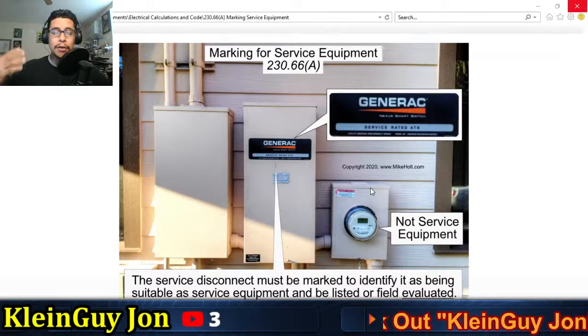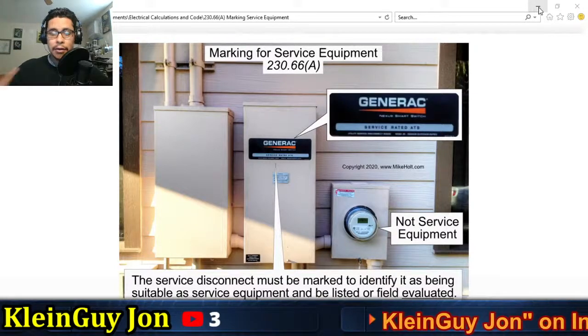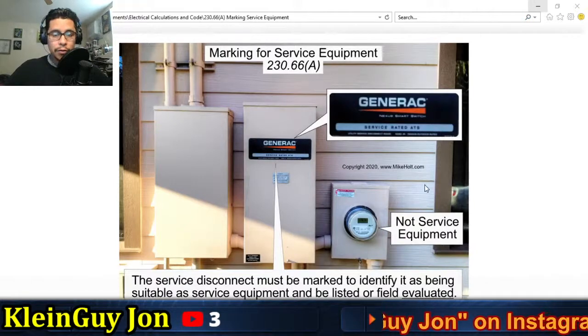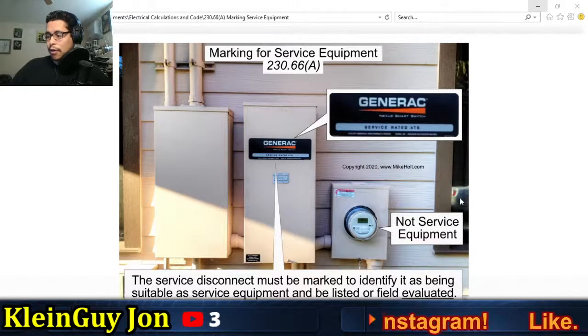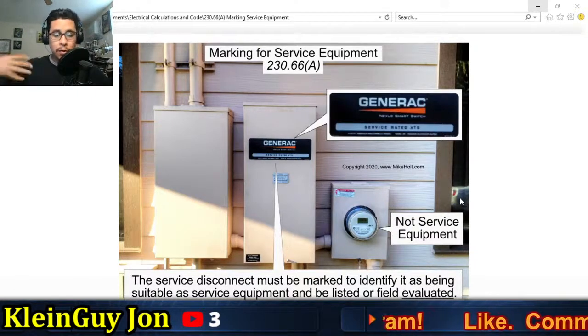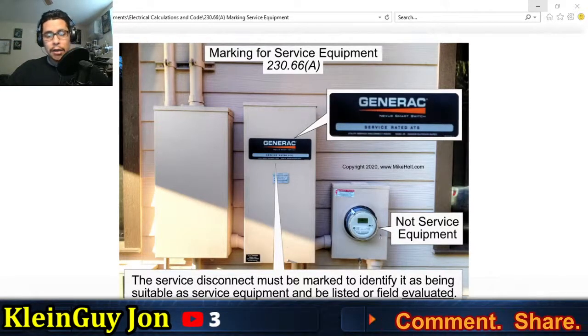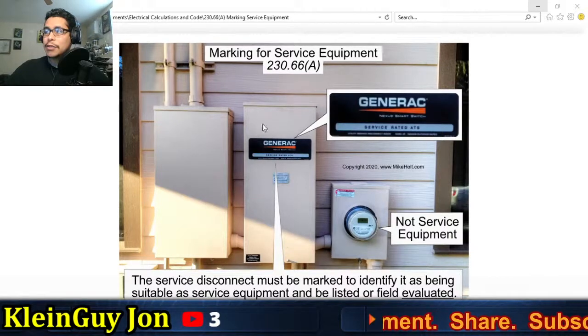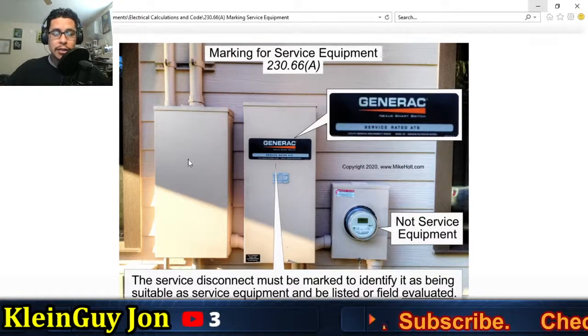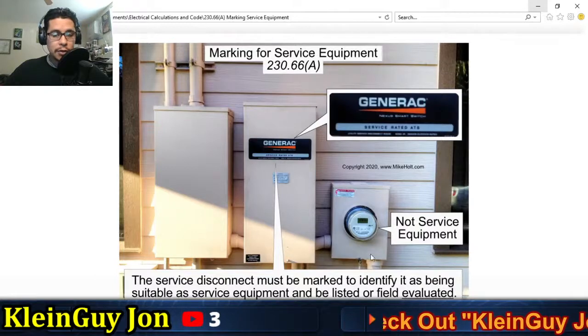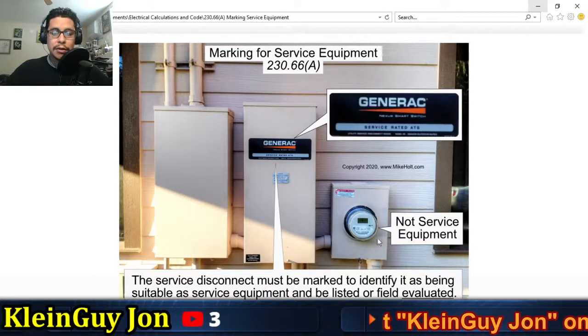What I'm gonna do is send this image out to the chat, I'm gonna call it the education chat in Microsoft Teams for all the guys I work with, because there's a lot of confusion. I hear a lot of them say, well, this is service. No, the meter is not the service. This is your service equipment right here, this is what disconnects, this is what energizes and de-energizes your system. This stays constantly on unless there's a power outage and it shuts off, but it is still not a service, it's not considered service.